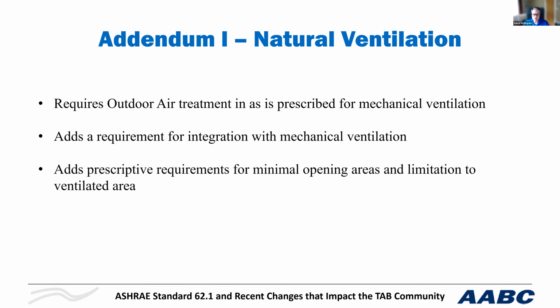Another interesting thing is that there are now prescriptions for the opening sizes for natural ventilation and their location. It makes sense, right? A certain size opening is going to produce a certain amount of outside air into a space. And there are also new limits on the distance from that opening that you're allowed to provide with that natural ventilation, which also affects the ceiling height, because as the ceiling height increases, the volume of the space increases, and you have to have more outside air to mix in with that indoor space.